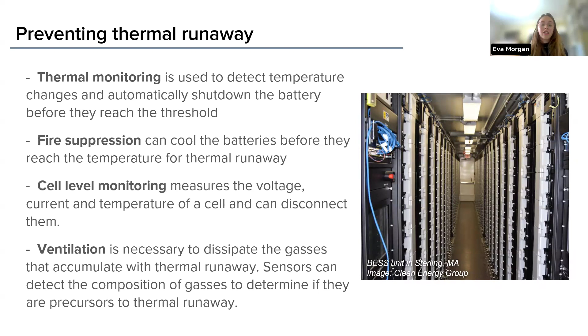The detection, prevention, and suppression methods have also really improved over the past decade. NFPA 855 has mandated fire detection technologies. There are also spacing guidelines that can mandate the maximum energy and spacing. Fire barriers can protect racks from propagating to other racks. Ventilation is really prioritized, which reduces the risk of explosion and thermal runaway. Batteries themselves don't explode, but if the mandated ventilation isn't there, the gases that accumulate can explode. Batteries themselves don't explode.